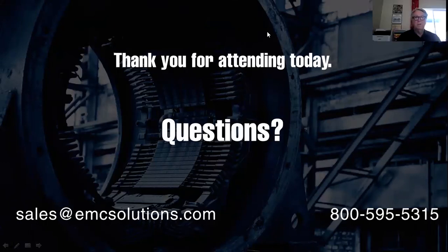I have another question from Chris that says, when should we be using EMC filters with VFDs? Oh, what a great question. This is where we a lot of times get into head scratching. So let me tell you my simple answer to this. In general, we're trying to hit 12%. Now, we see a lot of specs that want 5% current distortion, and of course that's great, but it is extremely difficult to get into. If you want a drive to generate 5%, the only technology that you have available is the active front end.